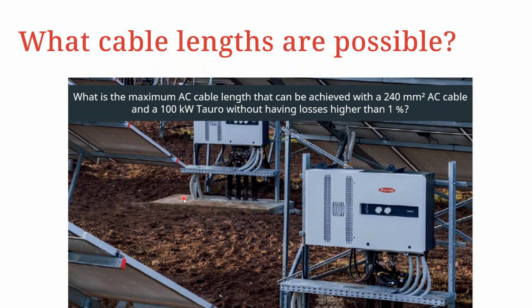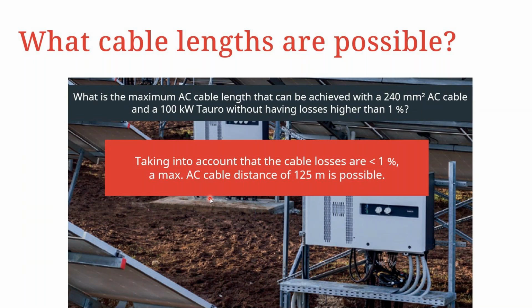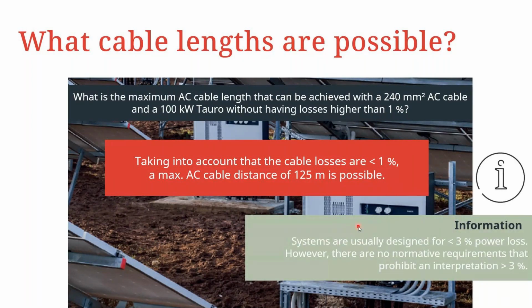We've done our homework on this. Taking into account cable losses, and trying to ensure losses stay below 1%, a maximum AC cable distance of up to 125 meters is possible, which is a very good figure. That said, it's also possible to design systems with losses higher than 1% but lower than 3%. There are no normative requirements that prohibit installations going higher than 3%, but of course the lower the losses, the better.